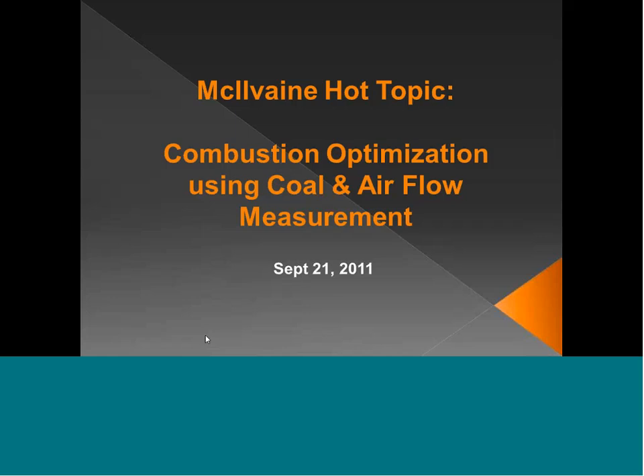Other questions? Hey, Dave, on the fineness, if you're looking to measure fineness, do you need to replace a section of the PA duct on the outlet of the mill? Well, I didn't fully explain fineness. I glossed over it, and to be honest with you, I only added these slides yesterday. We've been working on it for several years, but there are two different things we're working on. Because I say that slip is directly correlatable into fineness, we've built this device to very accurately measure the air and to measure the coal. Typically, we'd put it in one pipe out of a mill, assuming that the mill delivers the same fineness coal to each pipe.